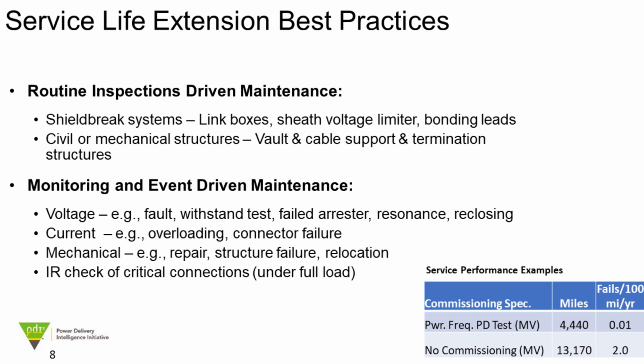Mechanical issues. We have a structure. We actually do some repair of a transformer or something. We have to relocate some terminations. When we touch it as humans, this is a good opportunity to go back and take a look at that baseline. And then using infrared inspection under high load conditions and low light to see, are those connections solid? And so we can do it just by using data. How did we actually touch the system, yes or no? And if we did, what did we do to the system?